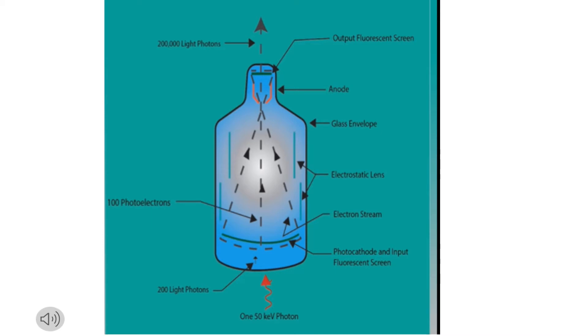First we're going to cover the fluoroscope. The first part is this input phosphor. It's made of cesium iodide. It receives the x-rays that come from the patient and produces light. So the x-rays are coming into the fluoroscope here and they hit this input phosphor and it's glowing, giving off light.